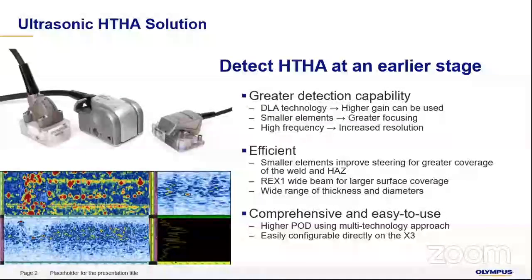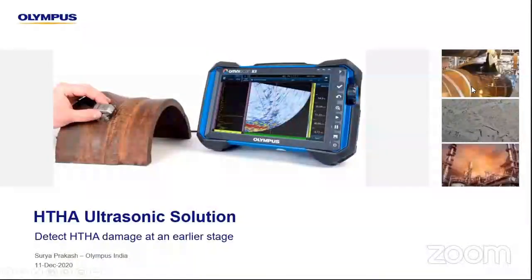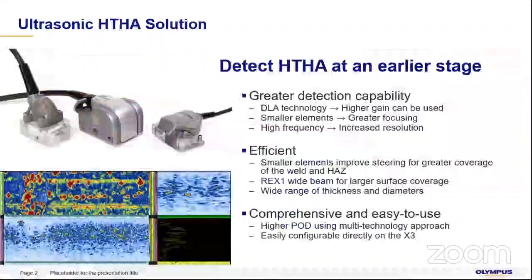HTHA usually happens when at higher temperatures hydrogen atoms fuse into the material of the pipeline and cause a weakening or softening effect on the pipes. As you can see in the images here, this weakens the strength of the pipe and causes rupture. Due to this, there have been cases in the US where HTHA has been taken as a much more stringent area of focus. For that, via Olympus, we have brought forth an HTHA series of probes which can be used for detecting HTHA at a much earlier stage, thereby helping prevent further disasters.